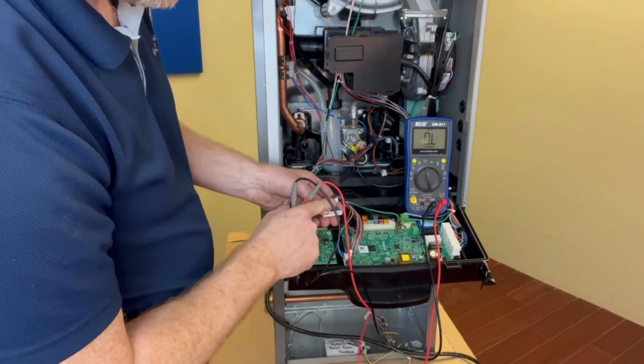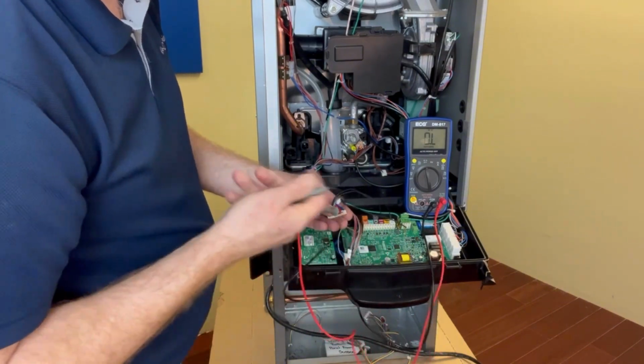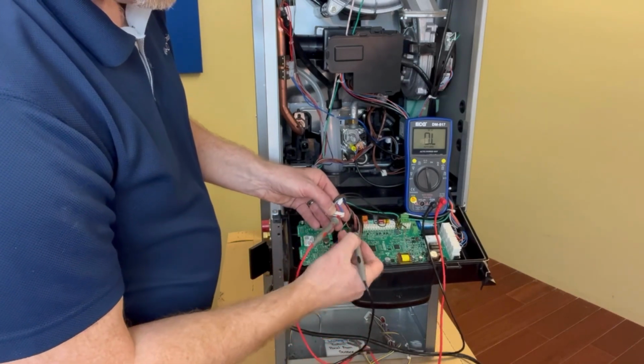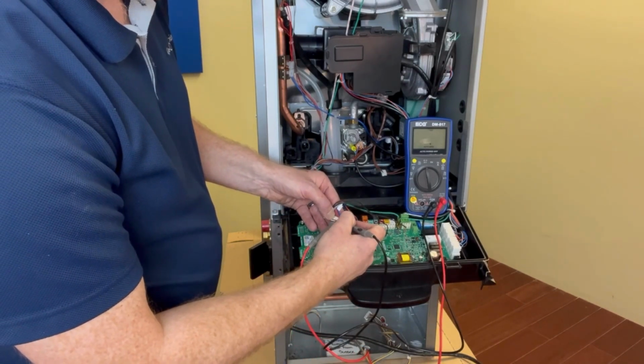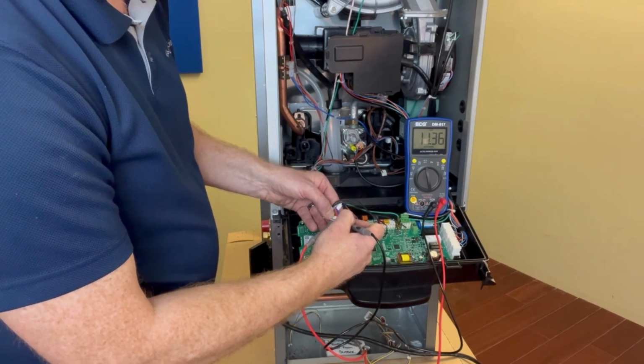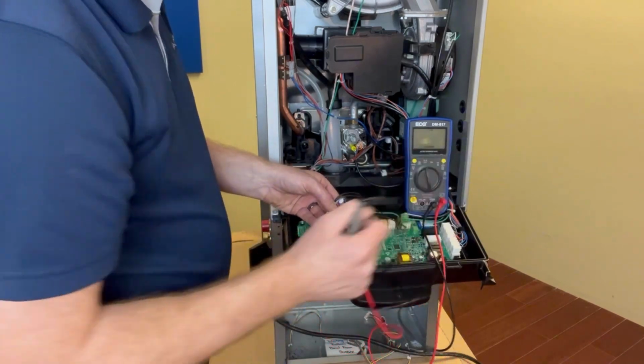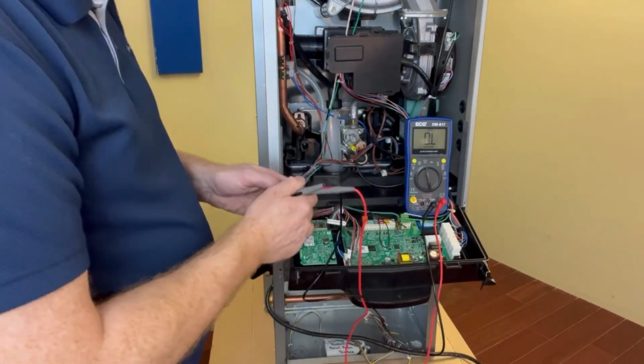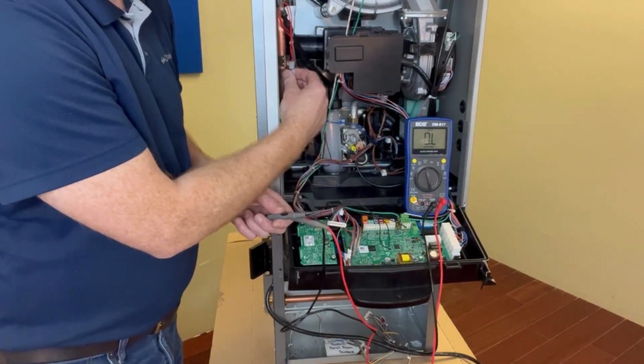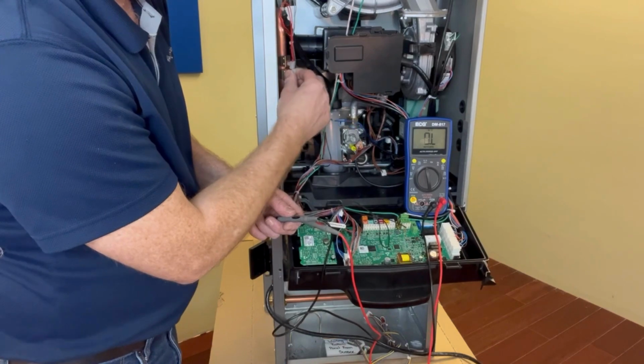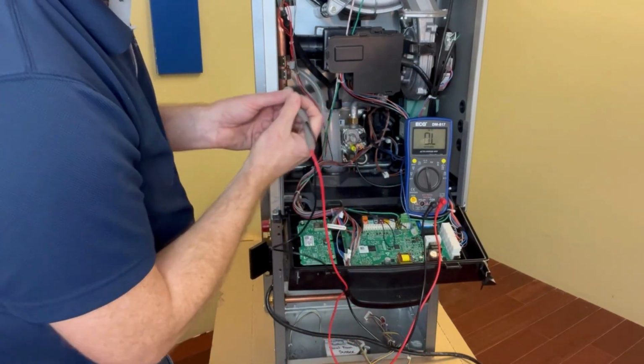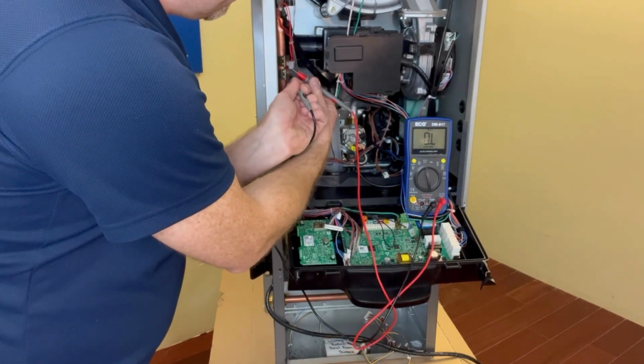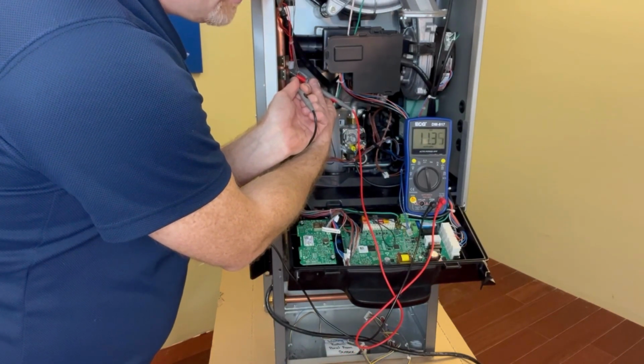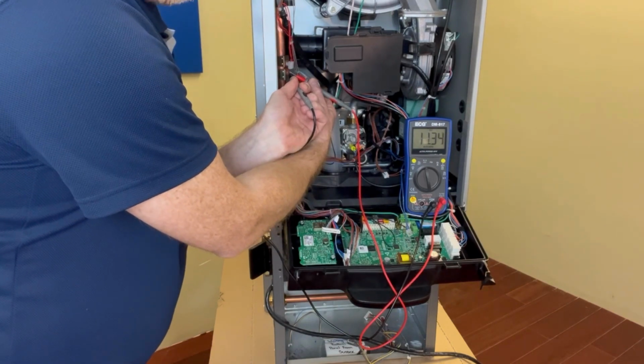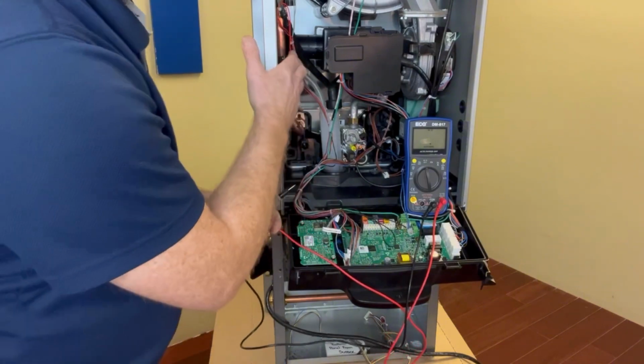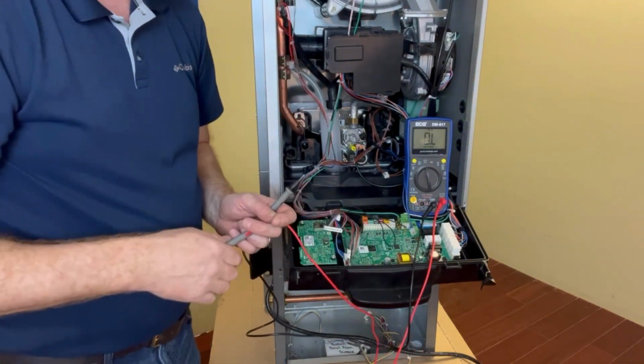Now let's do the same thing on the two blue wires, which is our return sensor. Gently press the meter lead in and touch the second connection, and we get approximately the same reading. If these differ by more than 1,000 ohms, it indicates that potentially one of these sensors is bad. Now, we saw 11.36 kilo ohms on the return sensor, which is the two blue wires. So what we're going to do next is go to the sensor itself and double check the reading that we get directly on the sensor. It's essentially identical to what we saw at the circuit board, which tells us that both the sensors and the wire harnesses are in good condition.